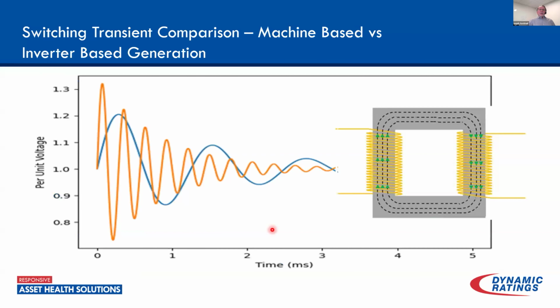Now, transients and overvoltages is one thing that I was a little bit surprised by. It's actually quite interesting. Here's a traditional switching transient for machine-based, or rotating machine-based, generation. Because of the inertia and the momentum, it resulted in a pretty stiff system. If we had a switching transient with machine-based generation, typically you'd max out at about 1.2 per unit when it came to the voltage. But what's interesting here is look at the frequency of that transient. Yes, there's maybe a high frequency component, but it was pretty short-lived. The remainder of it basically followed that 60 hertz pattern. So it was a short duration.